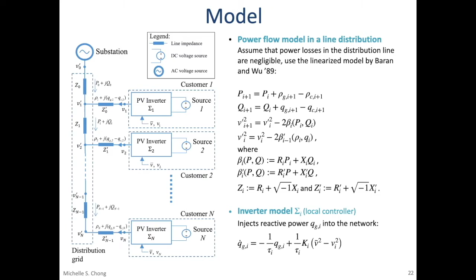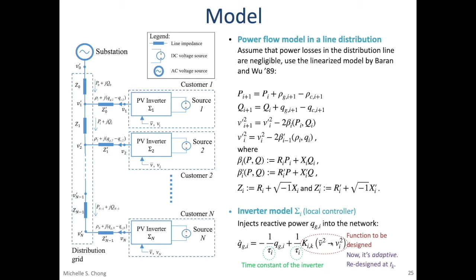The response of the inverter is modeled as follows, where tau I is the time constant of the inverter's response. Our objective is to design the function k to achieve the safe voltage regulation objective. Previously, this design was one-off, based on the upper bound on the data over all time. In this paper, we present an adaptive procedure where the function k is redesigned at each discrete time instant, which was predefined, based on the data over the time window, and we prove that the safe voltage regulation objective can also be achieved.